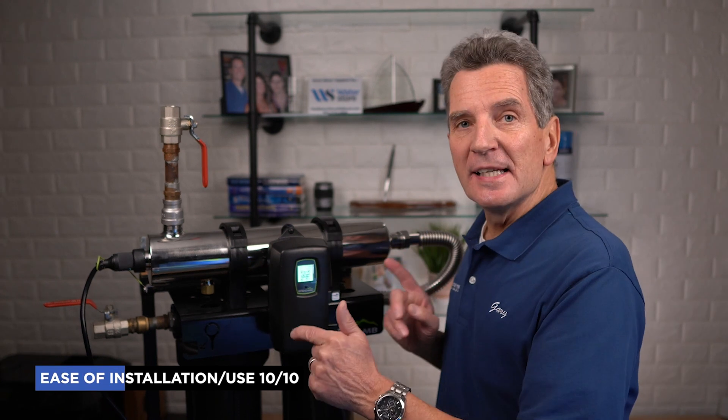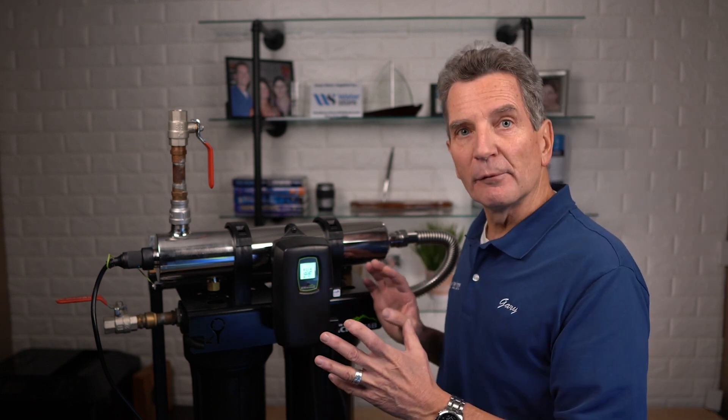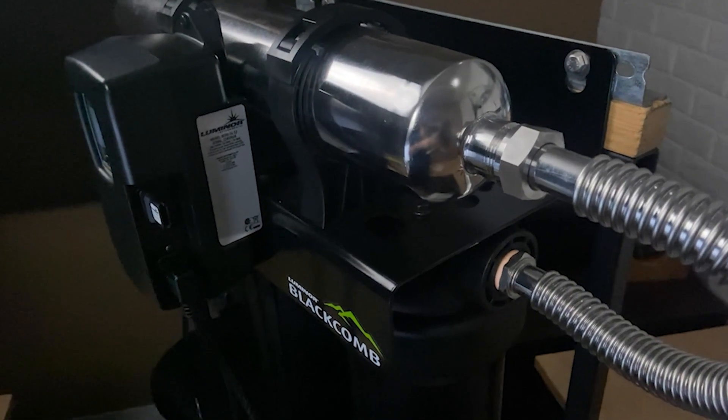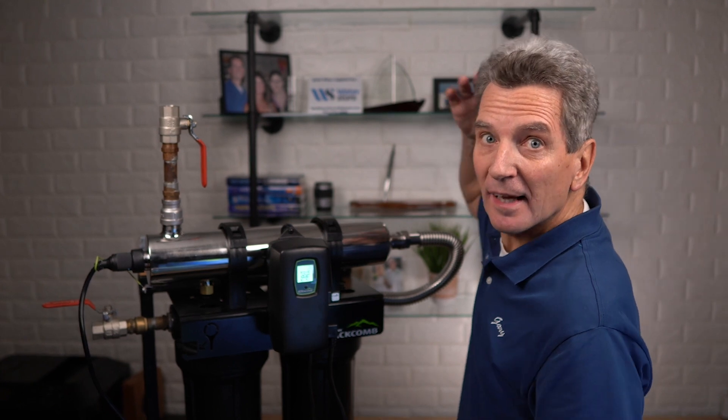In terms of ease of installation, I rate these a 10 out of 10. It comes pretty much mostly pre-assembled — there are only a couple of things you have to do, like put on the controller, put in the lamp, and connect up the fittings. One of the other things I really like is that you don't need a lot of space. Often in a cottage or cabin installation you might be in a crawl space. Some other brands where the lamp gets changed through the top require an extra 20 inches of space above the system. With the Luminor Blackcomb system, you slide the lamp out to the side, so you need less height.